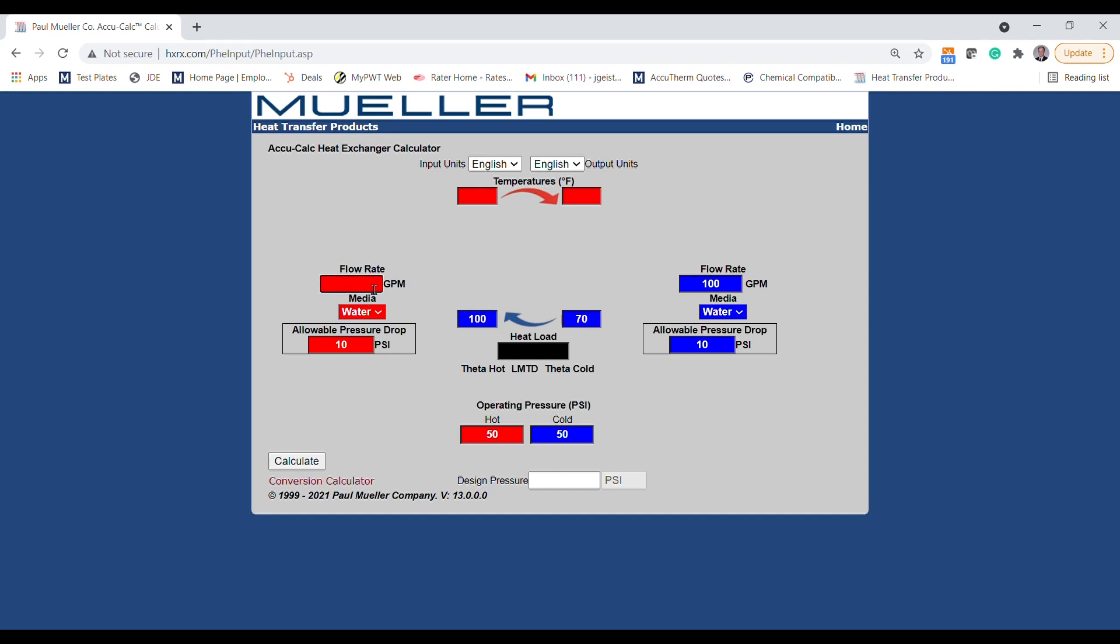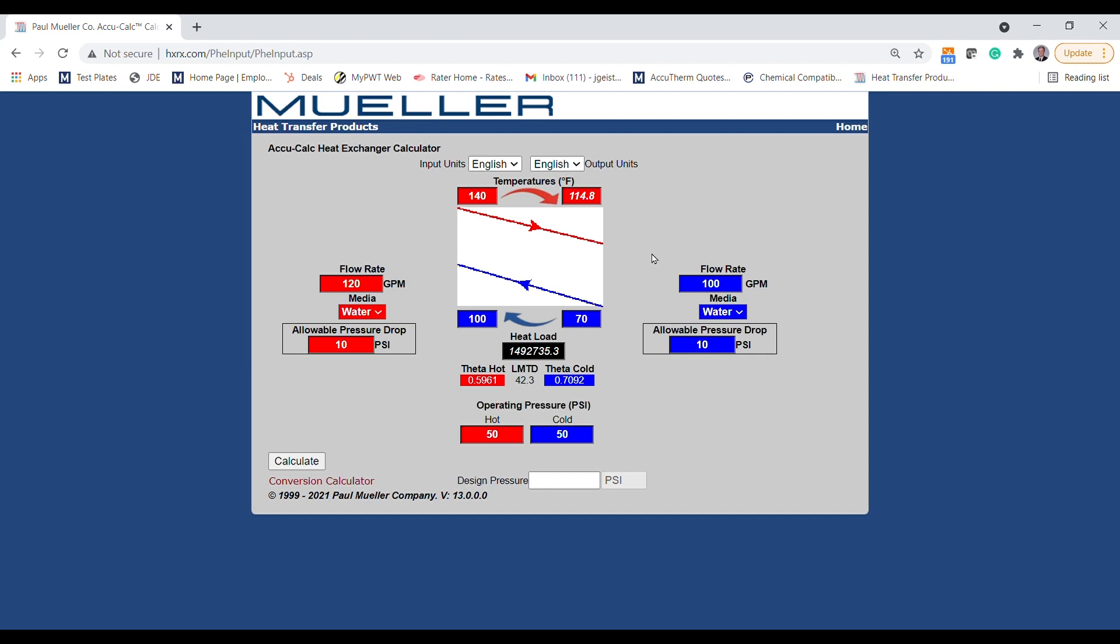Now let's also say that we have a boiler that can supply 120 GPM at 140 degrees Fahrenheit. As you can see, by entering five of the possible values, the final value is allowed to float, and we can now determine the return temperature of the hot water for the application at 114.8 degrees.